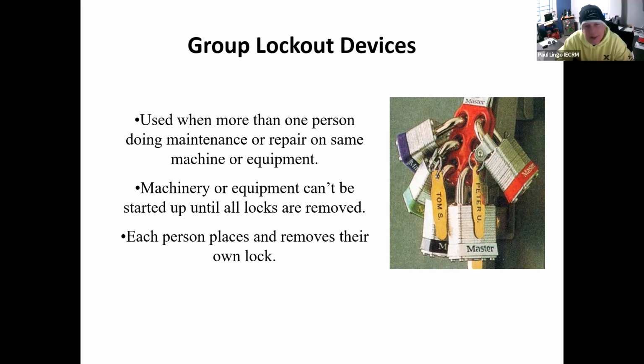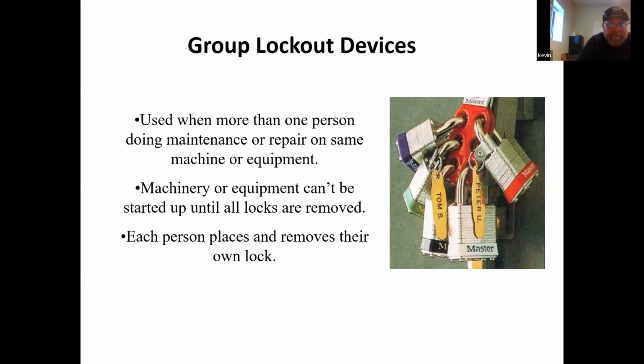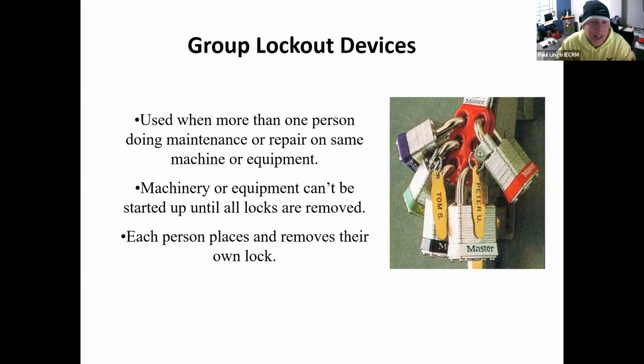Even just a journeyman and apprentice could be group lockout, tag out. That's good practice because you're both probably working on it, and you should both have a lock on there. It's important for the apprentice to start getting in the practice of locking and tagging things out every time, as a procedure and muscle memory. It's an ethic. Is it one person's responsibility to lock that tag out, or is everybody that's qualified to work on it responsible?